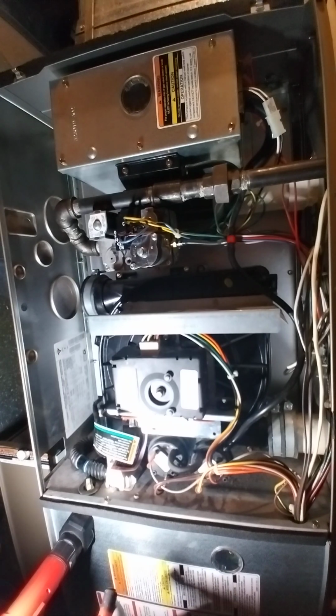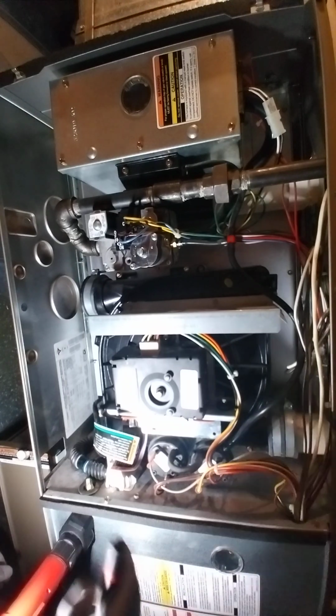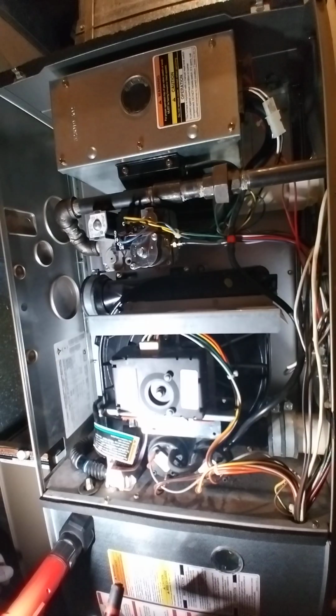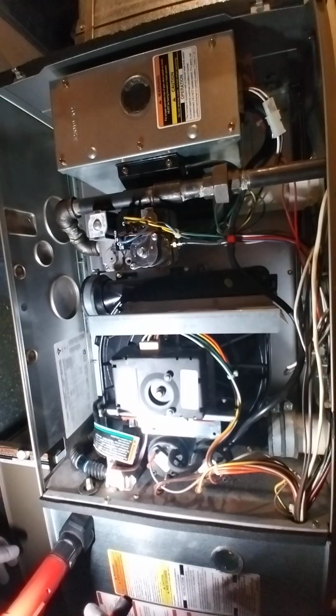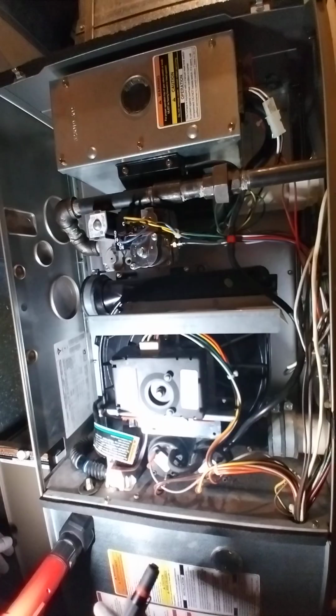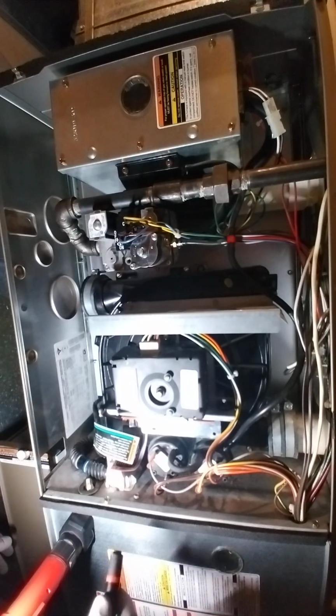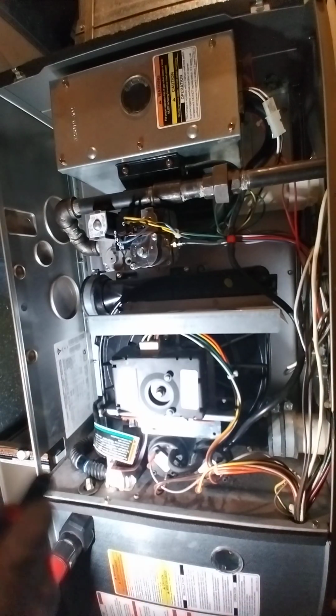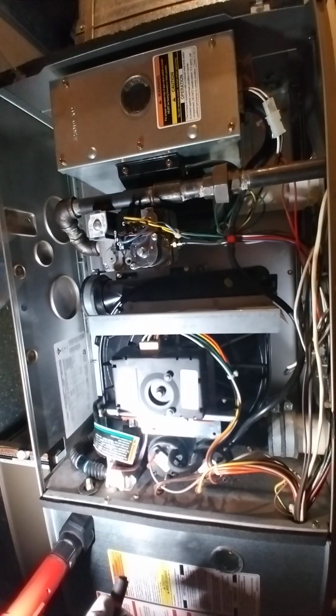So I checked that sensor. It was never tripping. I even had a thermocouple in the air system, the airflow itself. It never got up to a temperature high enough that would trip it. So that definitely wasn't the cause. The rollout sensor wasn't the cause. I was watching that. Plus, that's not a self-resetting sensor. I could watch the actual burner going in here, and it never came back to reach that sensor, and that sensor itself was never having any issues.